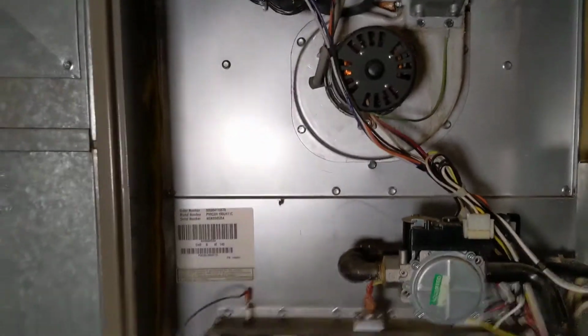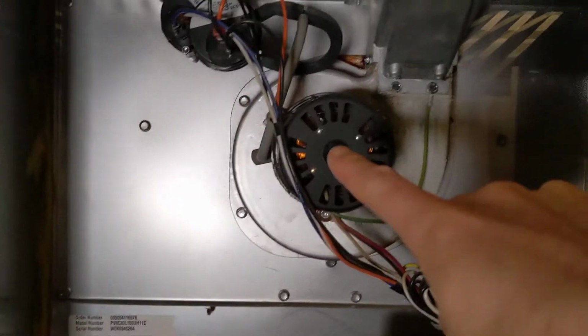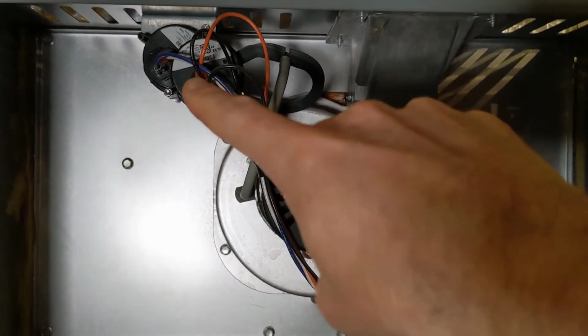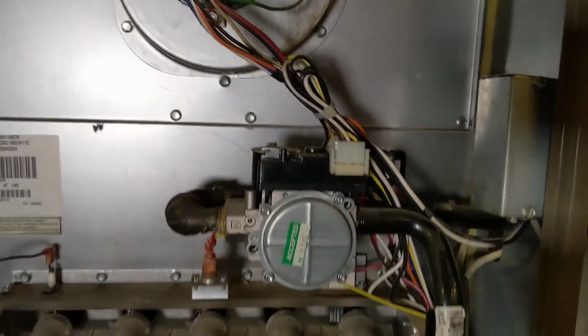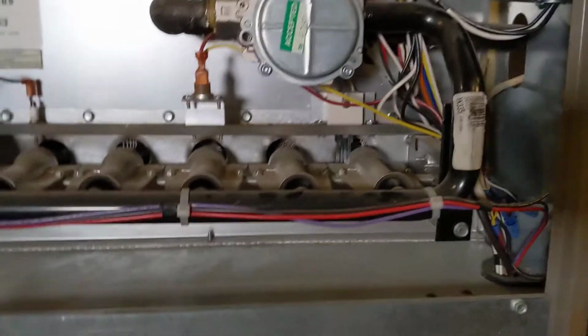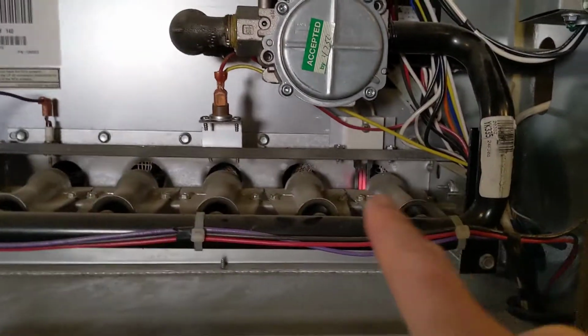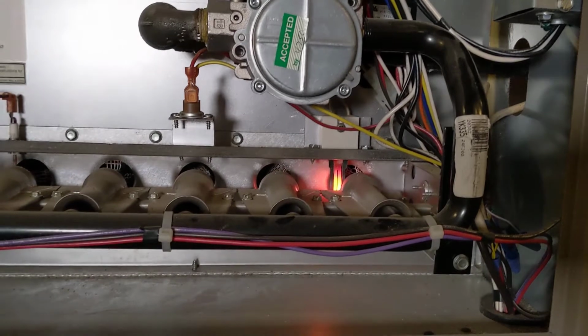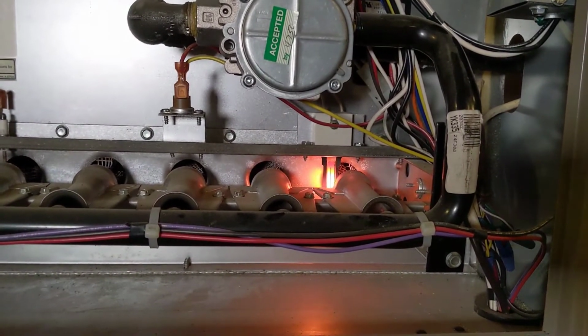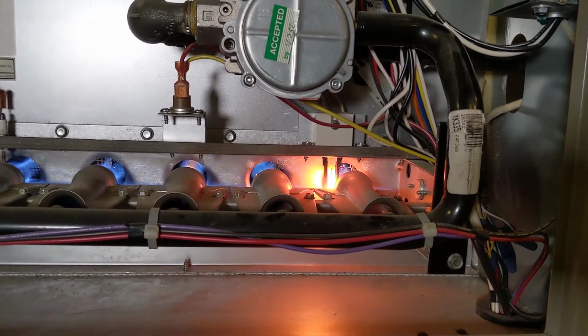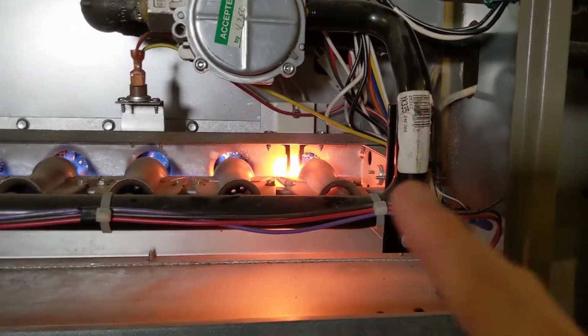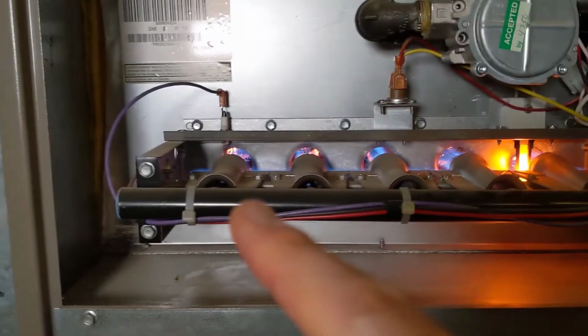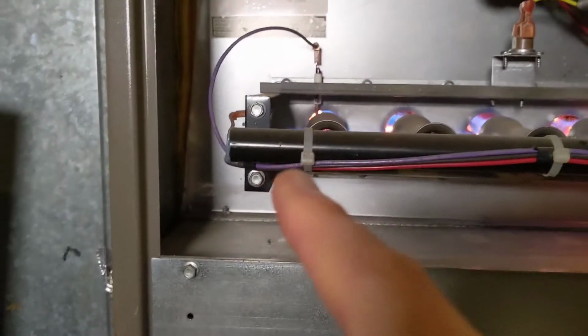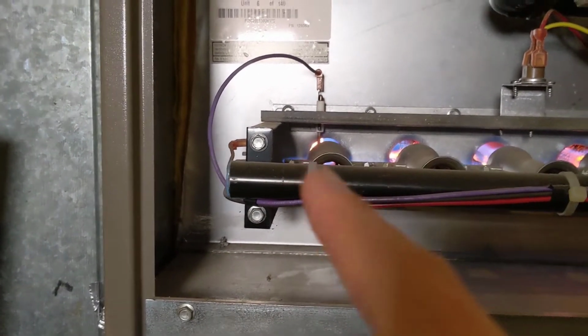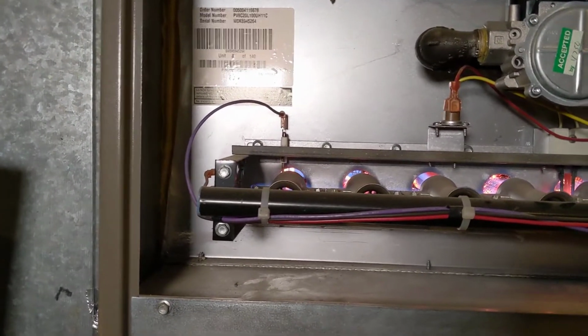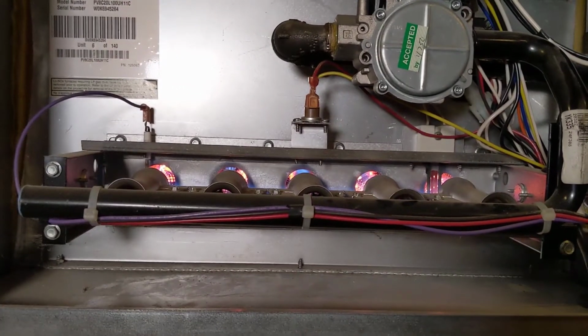Okay, so first thing you should hear is the inducer draft motor clicks on. That clicked that proof switch. Now we should see our gas start turning on, and we'll see our igniter starting to glow. Okay, that fired the first burner, which spread the flame to all the burners, and now we have the flame hitting our flame sensor, and so everything looks good here.